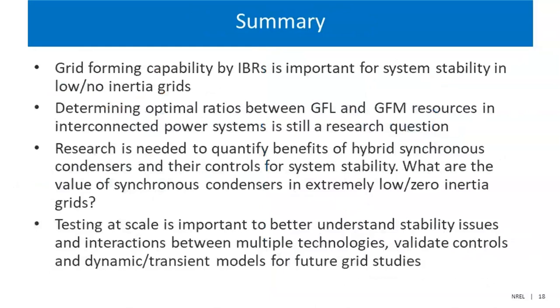And going back to my last slide, which is the summary and conclusion, pretty much everything I just said. So grid forming capability by inverter resources is very important, or it's an absolute must, I would say, for system stability with low or no inertia grids. Determining the optimal ratio between grid following and grid forming is still a pending question and is probably, again, very system specific. Research is needed to quantify benefits of this hybridization idea in synchronous condensers and their controls for system stability. And then what is the value of synchronous condensers in extremely low and zero inertia?